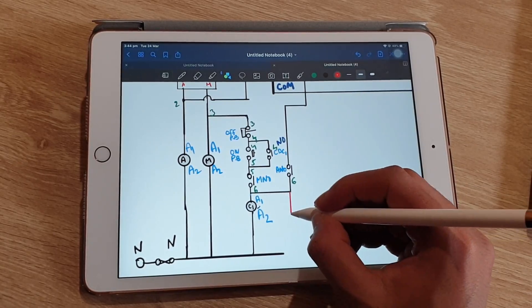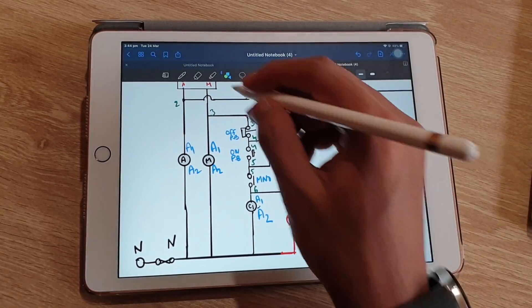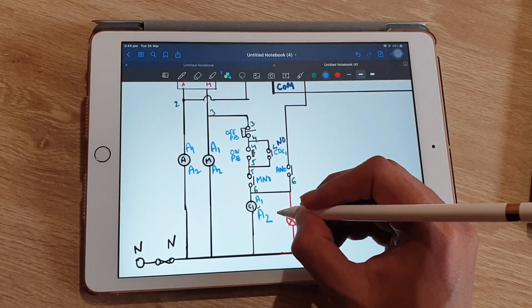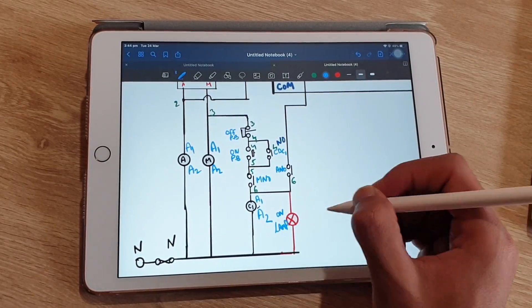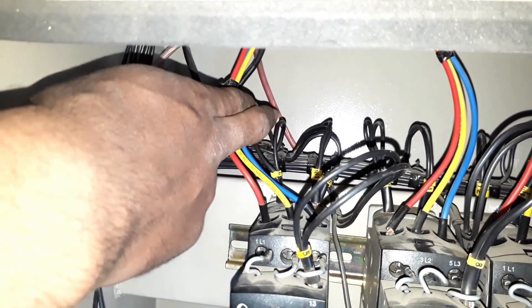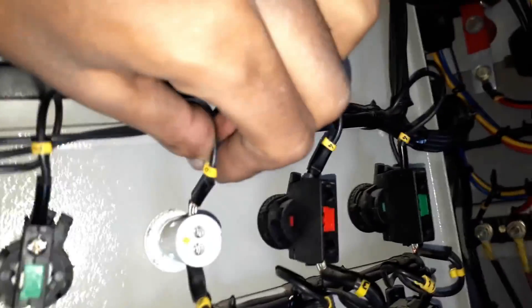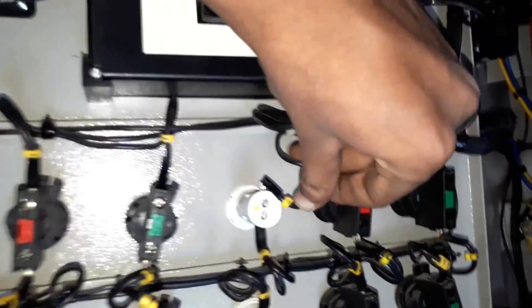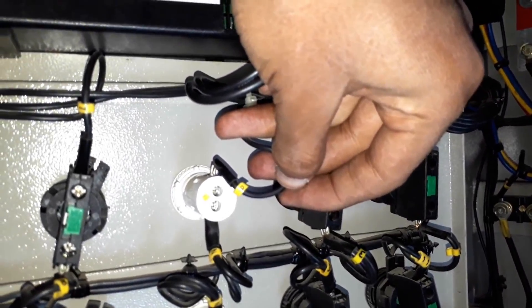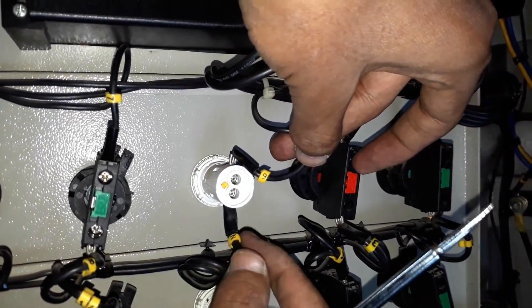After that, we have to connect a lamp from the A1 terminal of the capacitor duty contactor, and the other terminal of the on indicator is connected to neutral. So one wire is taken out from A1 terminal of CDC1 and connected to the on indicator — tagged as six — and another wire of the on indicator is connected to neutral.